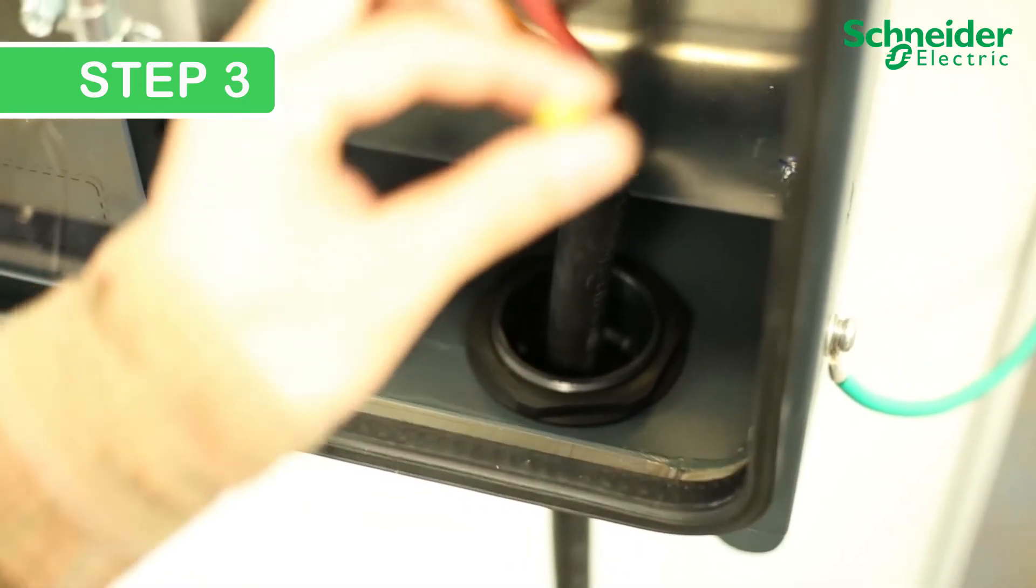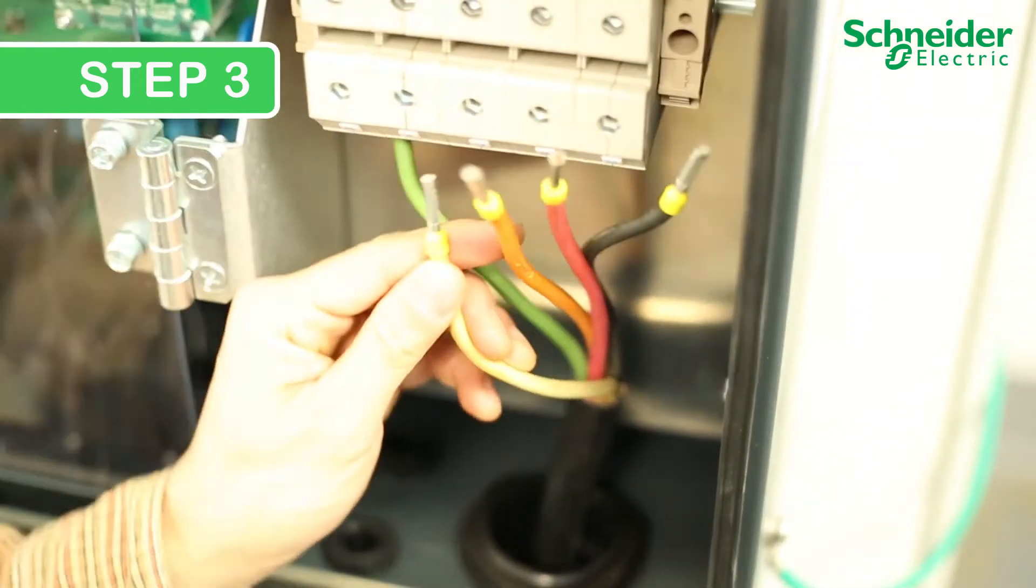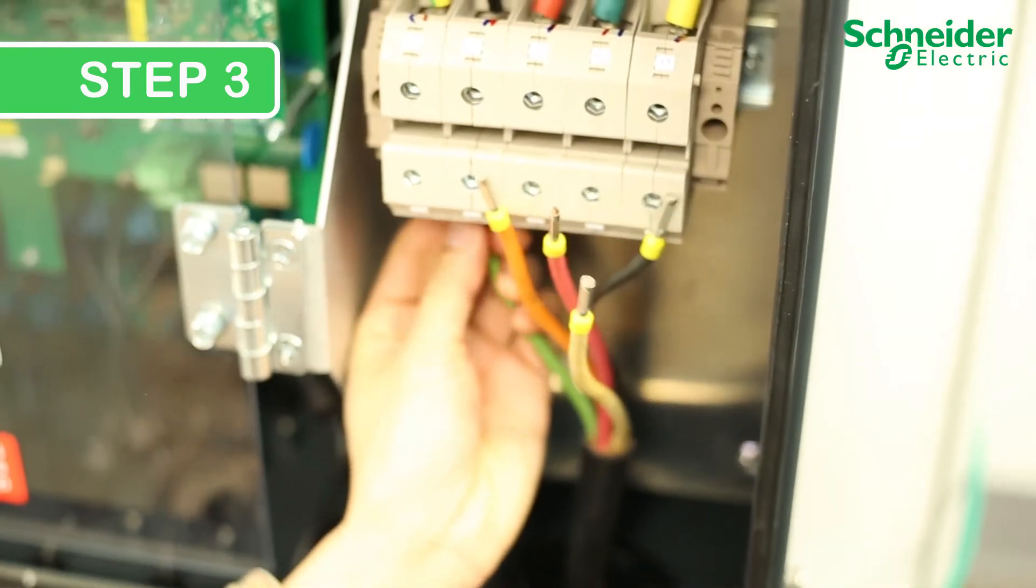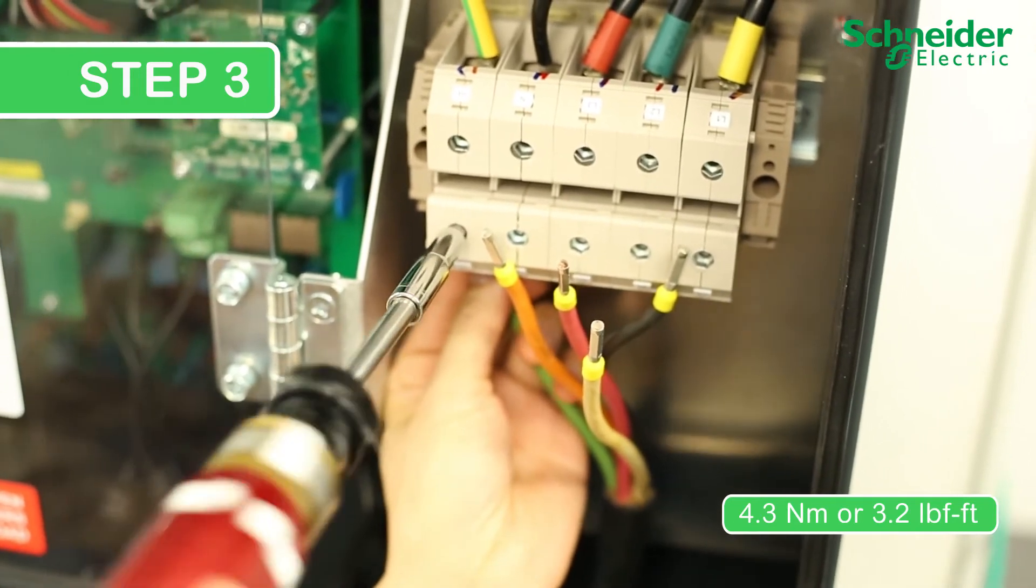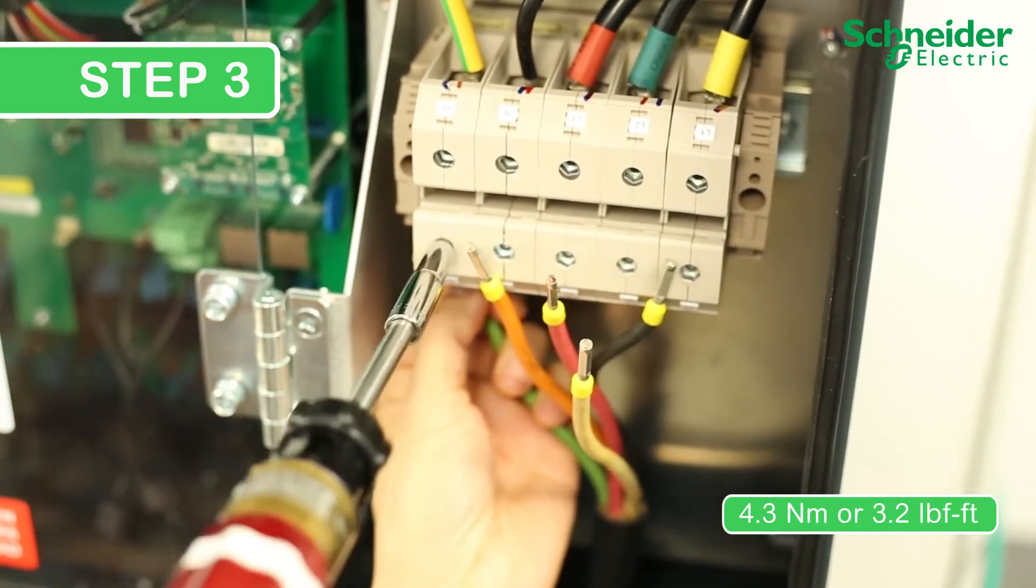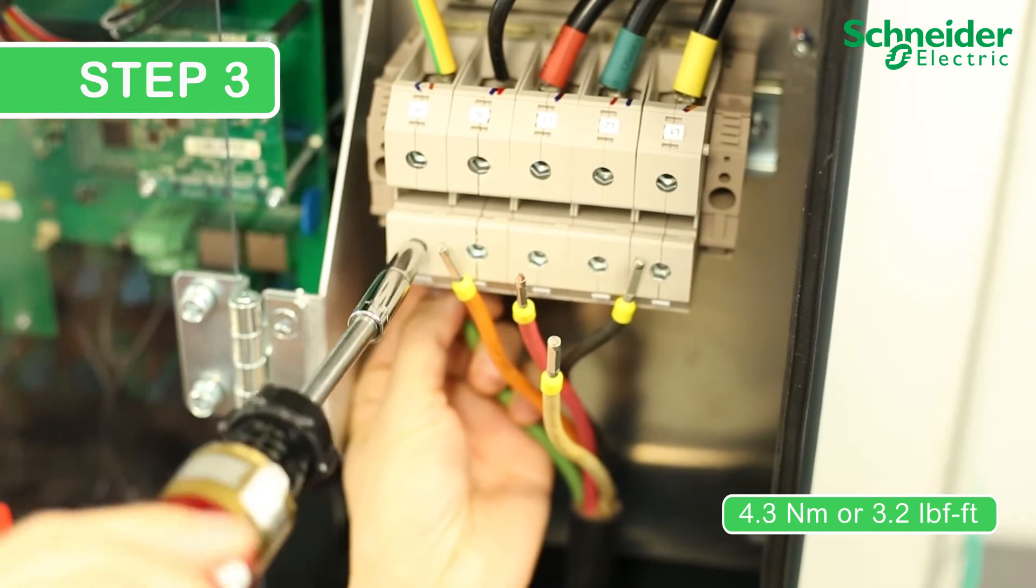Install the AC conductors on the CL60E starting with the ground wire. Ensure to correctly torque the terminals to 4.3 Nm or 3.2 lbf-ft. Ensure each phase is installed in the correct order.